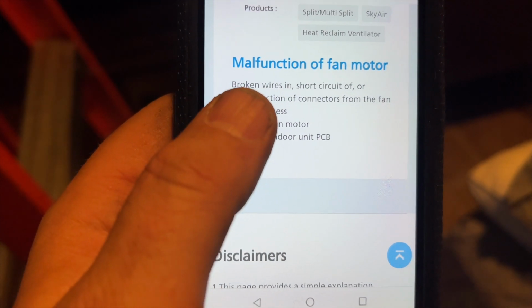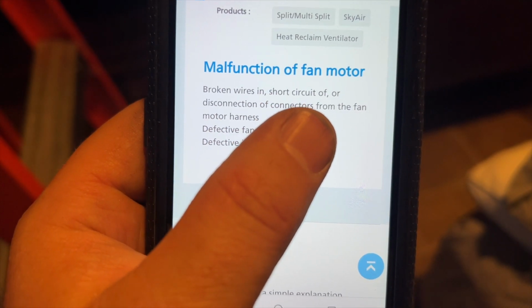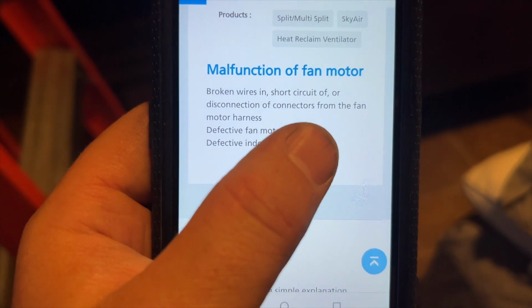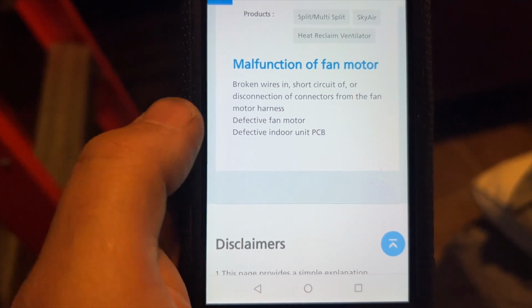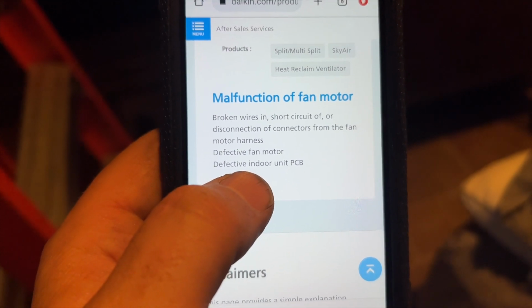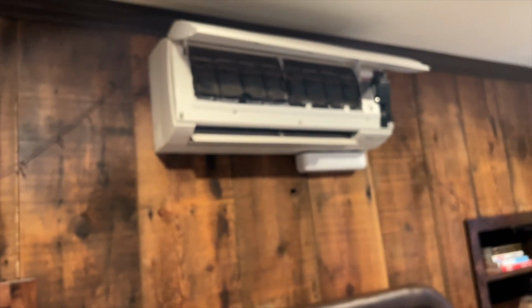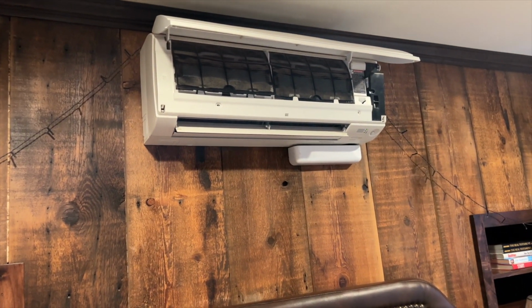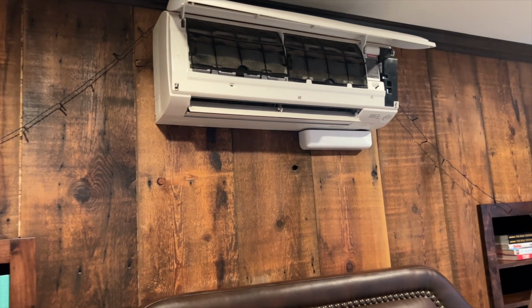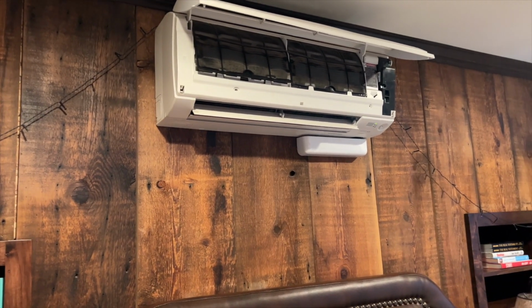So we have malfunction of fan motor, broken wires in, short circuit of, or disconnected connectors of fan motor harness, defective fan motor, or it could be a bad board on the indoor unit. So that's what we need to do now. So we're going to open this up and do some tests, because the downstairs one's cooling, it's working fine. So blower unit's not working, so it shut itself off.